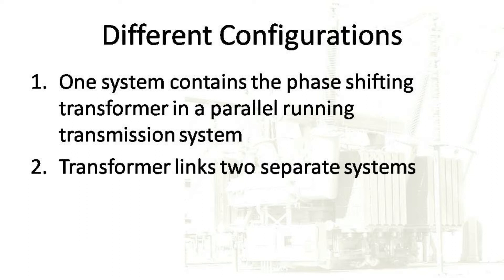Phase-shifting transformers work between systems that have the same sequence for both phase and frequency. The voltages can vary by both phase angle and magnitude. The unit design needs to be separated into two sections: one with an optimal, loss-free transformer that accomplishes the phase shift, and the other with a one-to-one turn ratio and equal impedance. Because of the power system's predominantly inductive character, an active flow of power between source and load must be achieved with a phase lag between the terminals.